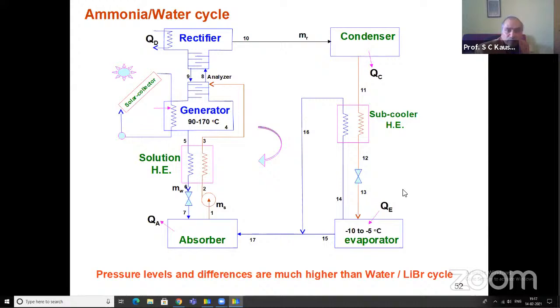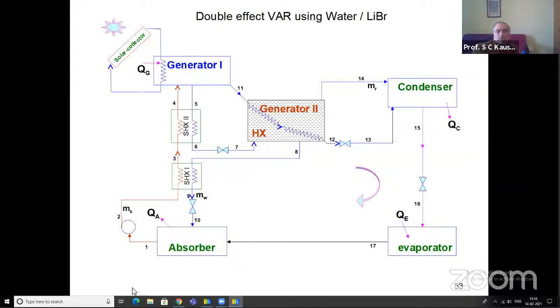But the problem is that even with a single cycle like this one, whether it is water lithium bromide or ammonia water, the COP is low. To provide more cooling capacity in the evaporator, we need a high collection area for providing heat input to the generator. This may not be suitable for any commercial or high technological application of these systems. So to improve the COP of the vapor absorption system, we have to use a double effect water lithium bromide combination.